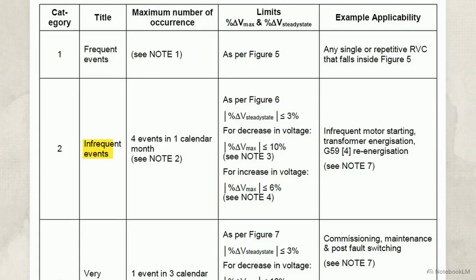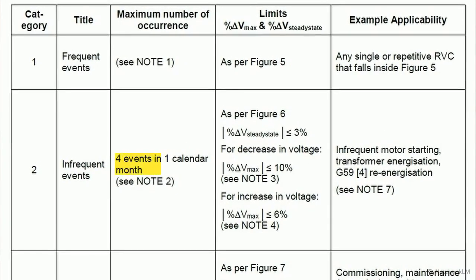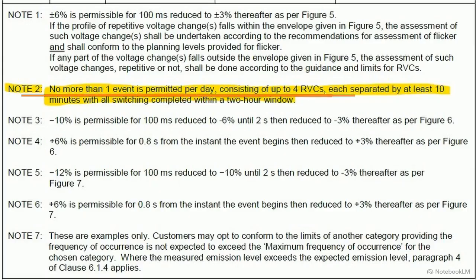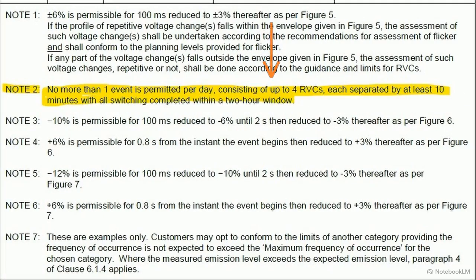This table defines the Category 2 RVC limits for infrequent events. Under these rules, the grid operator permits only 4 switching events per calendar month. The critical restriction is found in Note 2. It clarifies that only one of these events is permitted per day, and each event can contain a maximum of 4 RVCs, meaning 4 individual transformer energizations.